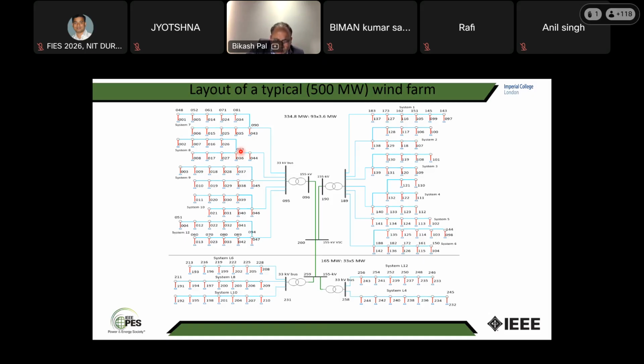So if I have a 1,000 megawatt power plant in offshore water, and it's a square wind field, I'll have 15 kilometer by 15 kilometer, which is a lot of distance. When you are flying over the sea where there is an offshore wind farm, from the aircraft window you can see the whole wind farm, and it appears to be within 2 or 4 square kilometers, but it is not, because you are so high, maybe 15,000 to 20,000 feet up, so it appears very small. The thing I want to tell you is that there are a lot of cables. The cables have dynamics, then it comes to the transformer, and then finally to the 155 kV voltage source converter.